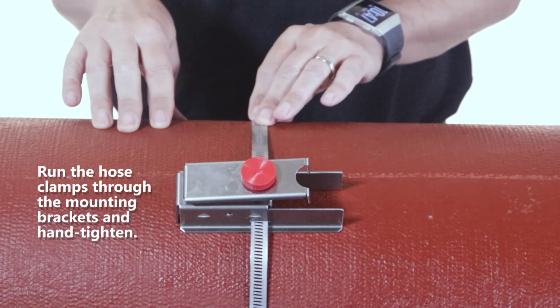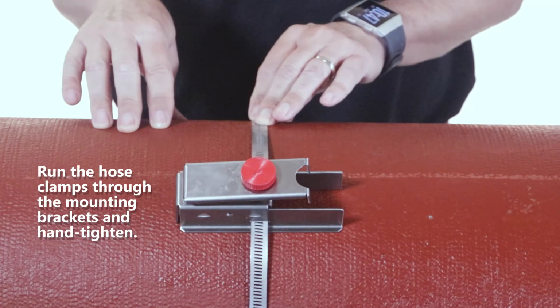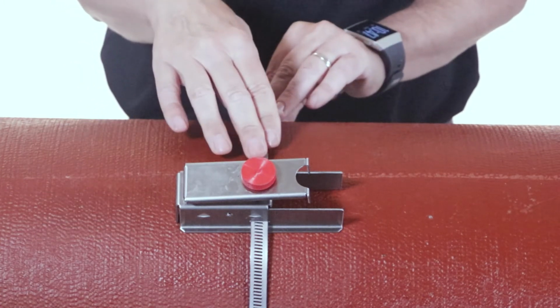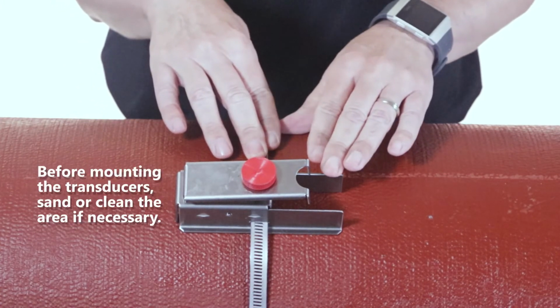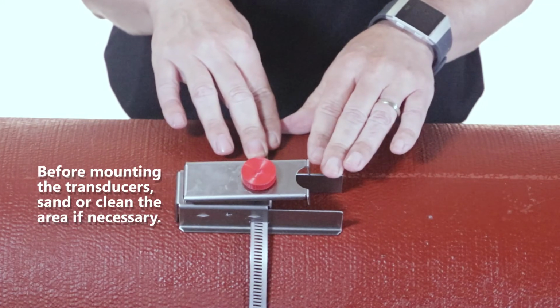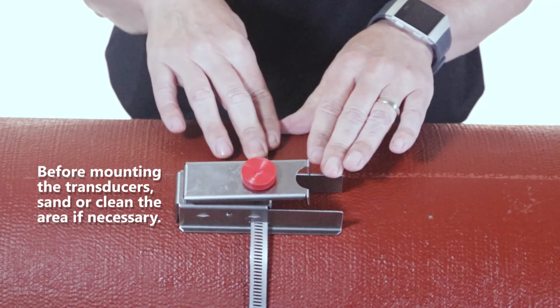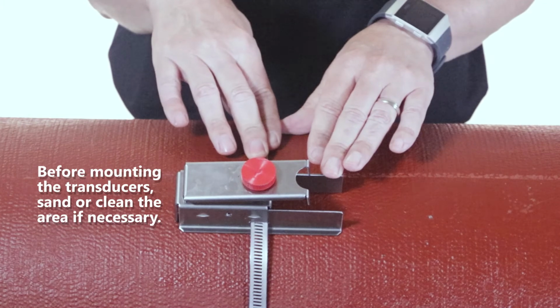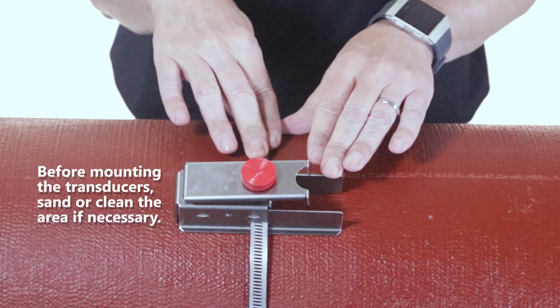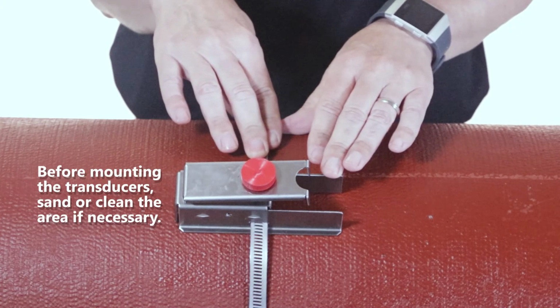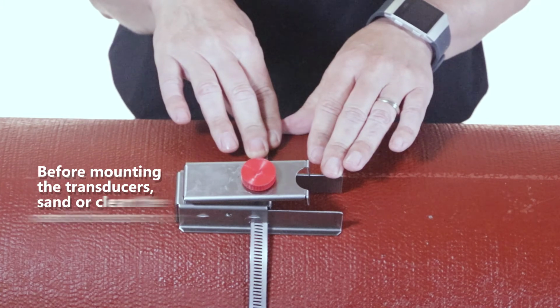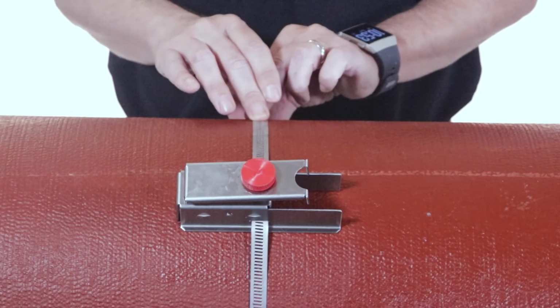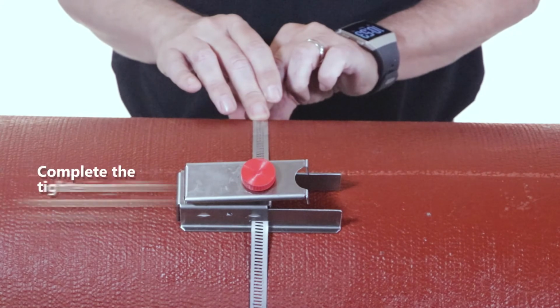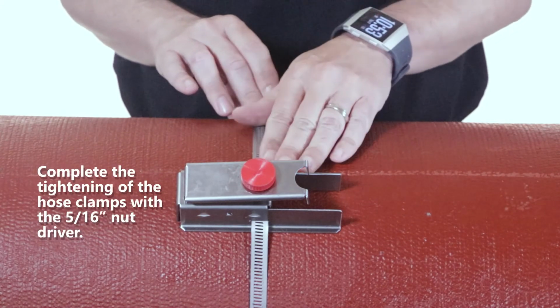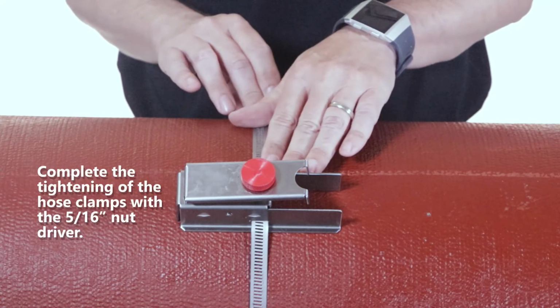As you can see, I've already run the hose clamp through the mounting bracket and hand tightened. We hand tighten in case any small adjustments need to be made during the setup. For our application, the pipe is clean. However, if you have a dirty or corroded pipe, you may need to clean it. Also, if you have non-bonding paint, you may need to sand an area for both sensors. Remember that our mounting bracket is only hand tight at this point. Once we've found the correct spot for the mounting bracket, remember to tighten it with the nut driver.